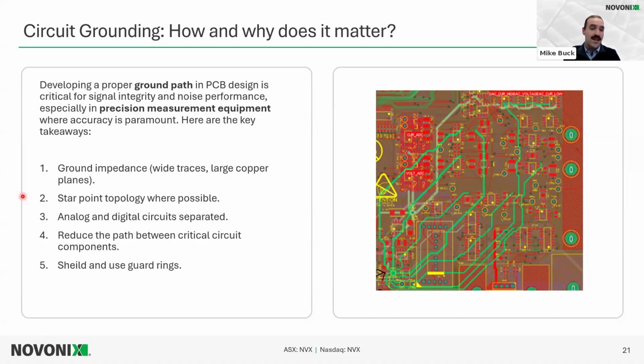We try to use what's called a star point topology. This forces return paths for the currents to go to a single point, so that when you're voltage referencing your ADCs, they're as accurate and tight as possible. If they went to different places on the PCB or different places within the instrument, you'd get voltage differences that throw off the measurement readings you eventually see on the software screen.